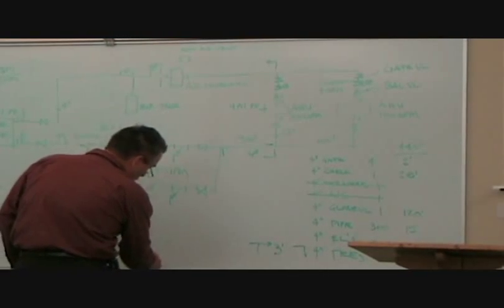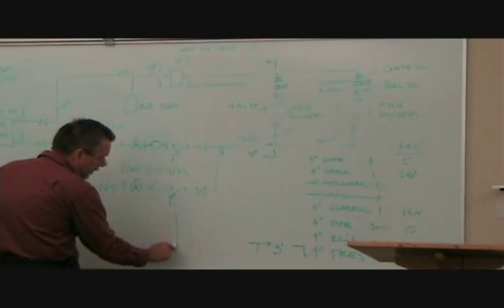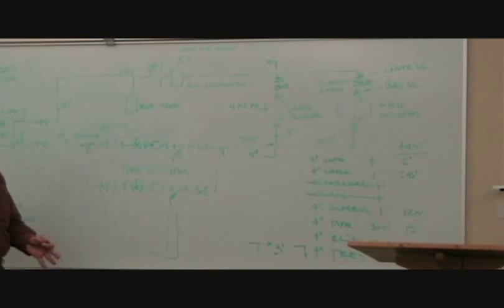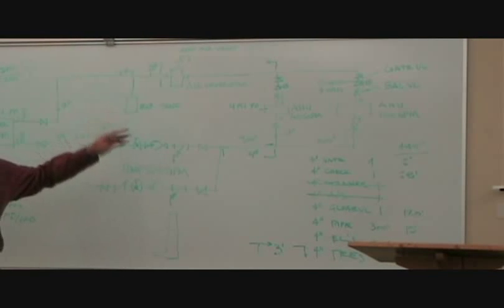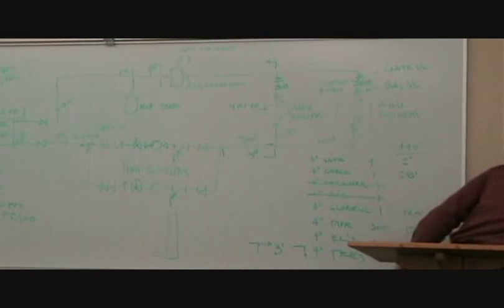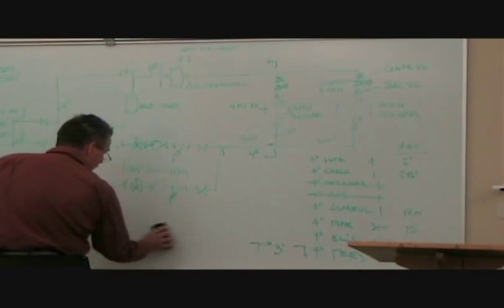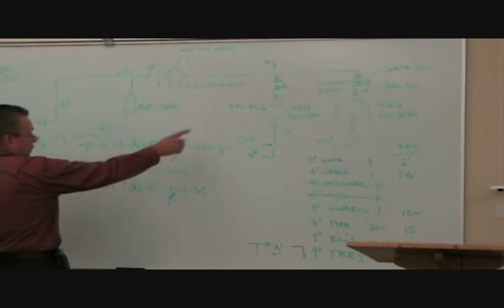Now, this is a closed piping system, meaning that if I'm on the ground floor, I got to pump up to the top of the building, a 10-story building, and I come right back down. It's a closed piping system. I got just as much head going up as I do going down, so I don't add any head to my pump. Now let's compare that to a cooling tower. Same piping system. This could be the chiller, this could be the cooling tower. So I'm pumping out of the cooling tower into the chiller, back to the system. But a cooling tower generally is an open piping system.